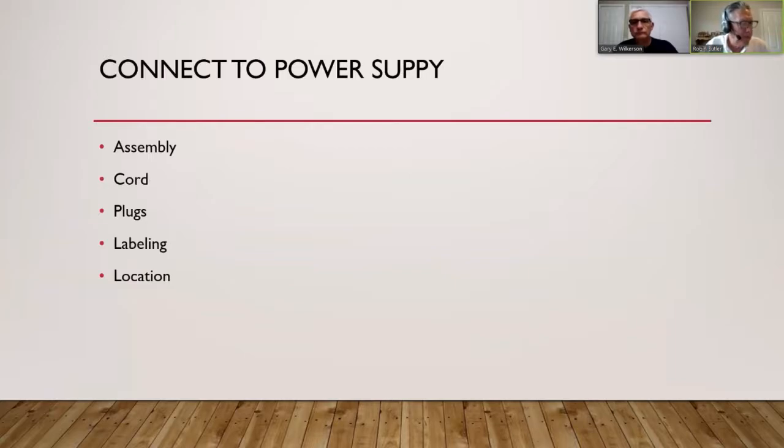Cool. And then also in this same section, it has the configuration of a 30 amp, 125 volt, 2-pole, 3-wire with a ground, and a 50 amp, 125/250 volt, 3-pole, 4-wire with ground type of plug or outlet. And they have receptacles and they have caps. Caps would be the plug. So they show you what a receptacle looks like and what a cap looks like.